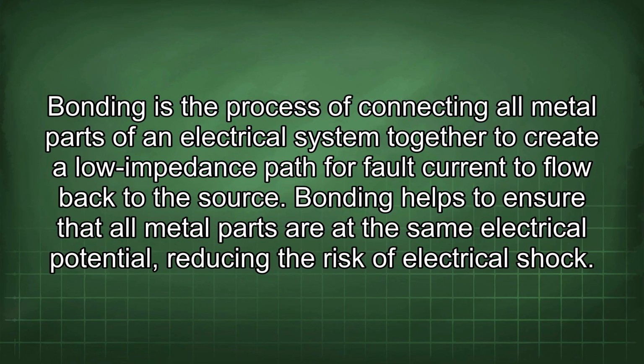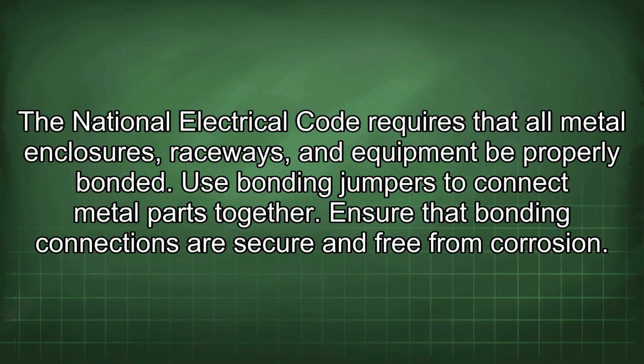Bonding is the process of connecting all metal parts of an electrical system together to create a low impedance path for fault current to flow back to the source. Bonding helps to ensure that all metal parts are at the same electrical potential, reducing the risk of electrical shock. The National Electrical Code requires that all metal enclosures, raceways, and equipment be properly bonded.